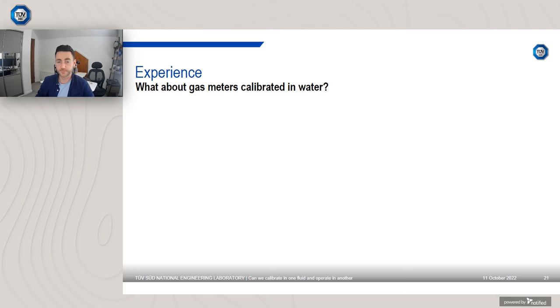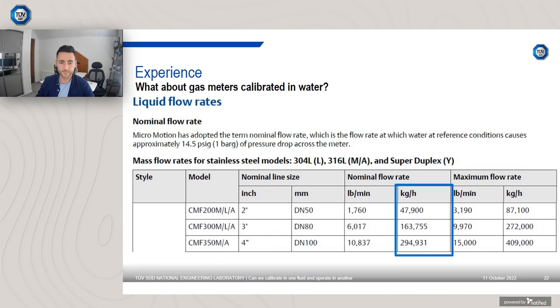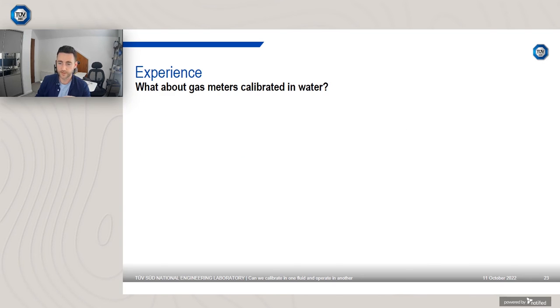And I have some slides here just to demonstrate what I mean. So I've taken this just from the manufacturer's guidelines. Oops, sorry, once again, just waiting for it to load. It'll load up in a second. Yes, hopefully you can see that now. So what I have here is the liquid flow rates from the manufacturer's guidelines for a 2-inch, 3-inch and 4-inch meter. Now what we're looking at here is the nominal flow rate. You can see I've got the blue rectangle highlighting the nominal flow rate for a 2-inch, 3-inch and 4-inch Coriolis meter. Fairly significant. Try and remember these numbers, but there's not going to be a test on it, so it doesn't matter if you don't get it correct, but they're fairly significant. Let's call the 3-inch mass flow rate 160,000, so 160,000 kilograms per hour.